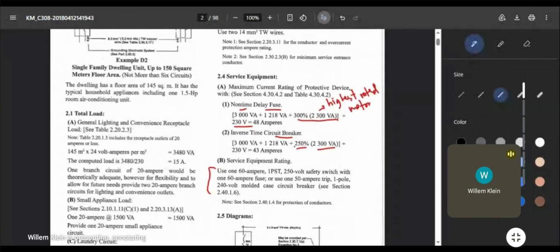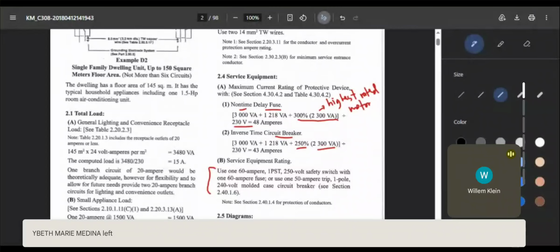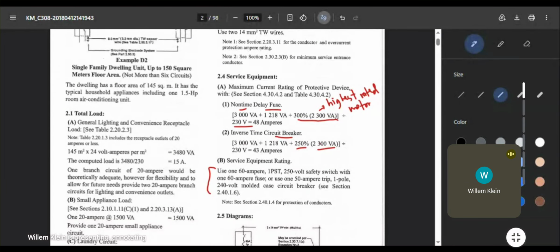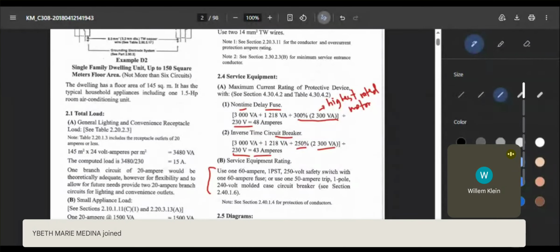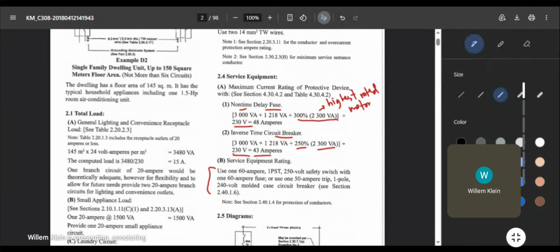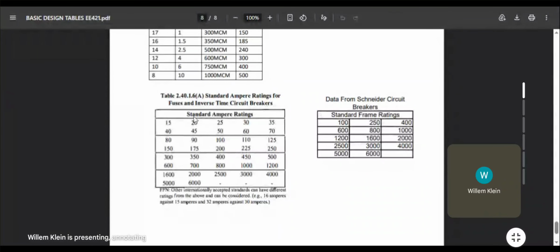So again, for the circuit breaker, that's 250% of your highest rated motor, and the total of this divided by your supply voltage. Again, in this case, 230 volts. So it's computed here as 43 amperes. When you look at the table here, the standard ampere ratings for inverse time circuit breakers, as you can see there's a 45. But that's too close for comfort for your circuit breaker.